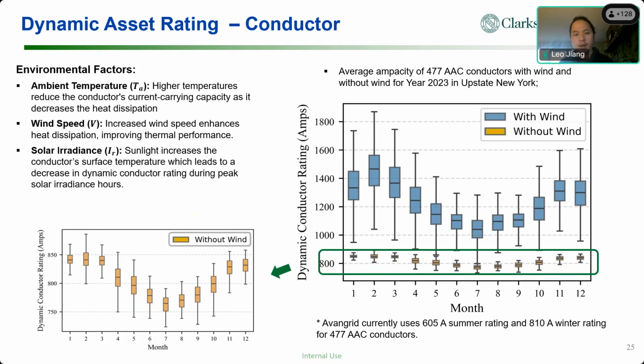I'm using the 477 all aluminum conductor as an example here. We're using the year 2023 data near Rochester. We're trying to do the thermodynamic study for the conductor thermal rating, both with wind speed and without wind speed, to see what loading current the 477 AAC conductor can bear. Just for comparison, currently Avangrid uses 605 amps for the summer rating, and 810 amps for the winter rating, for 477 AAC conductors.